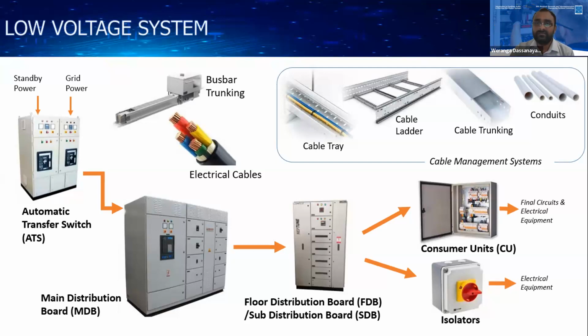That's how power is distributed among a low voltage electrical distribution system. So when you are going to do an audit in an electrical distribution system, you have to clearly identify what is the automatic transfer switch, what is the main distribution board, what are the floor distribution boards, what are the sub-distribution boards, then what are the final distribution boards, that means the consumer unit.